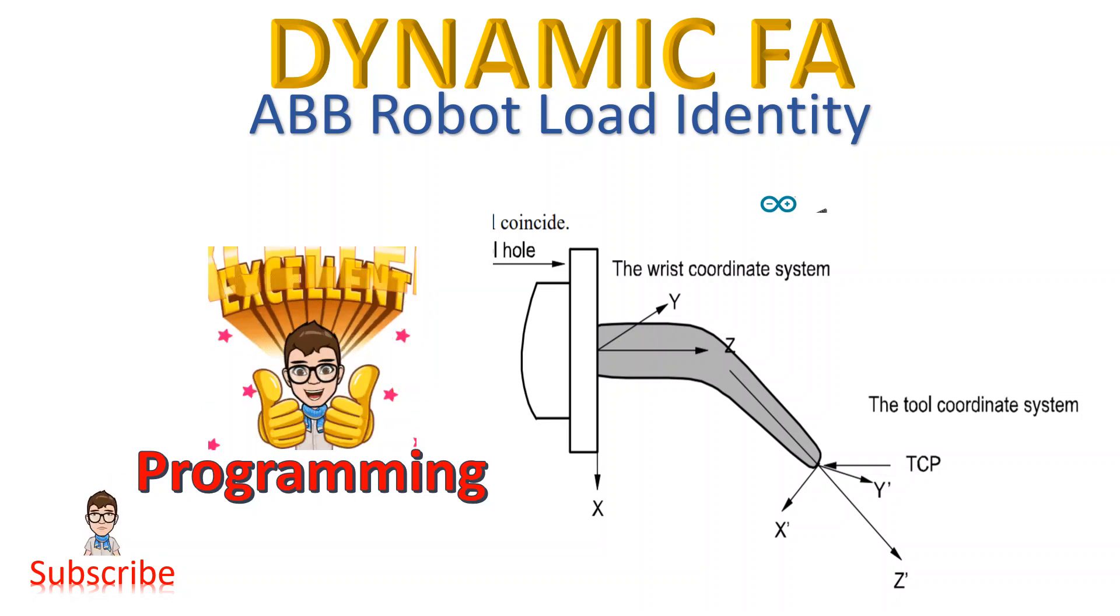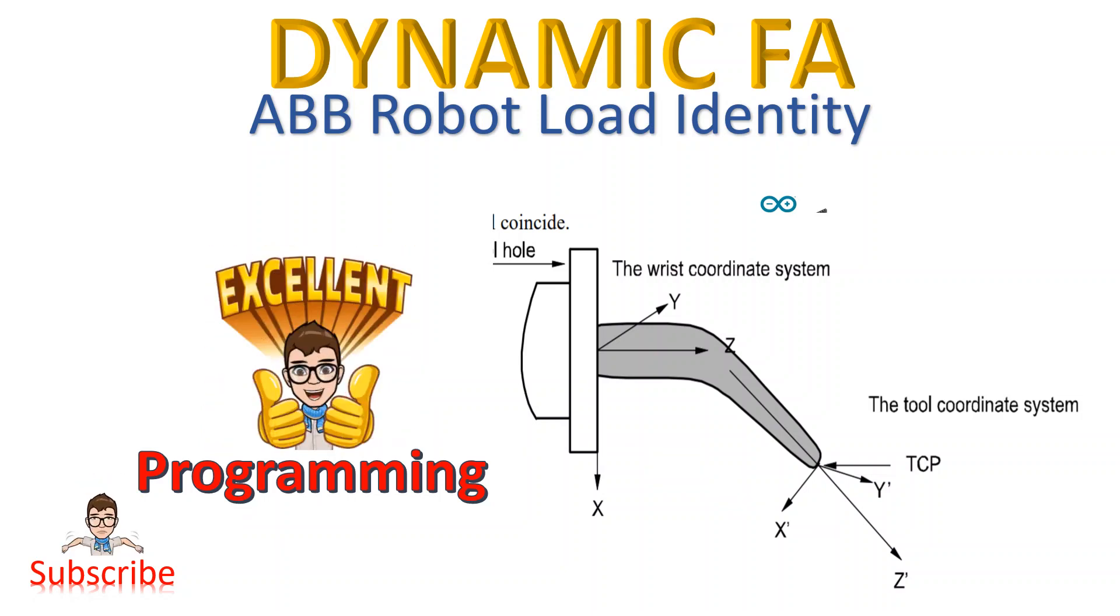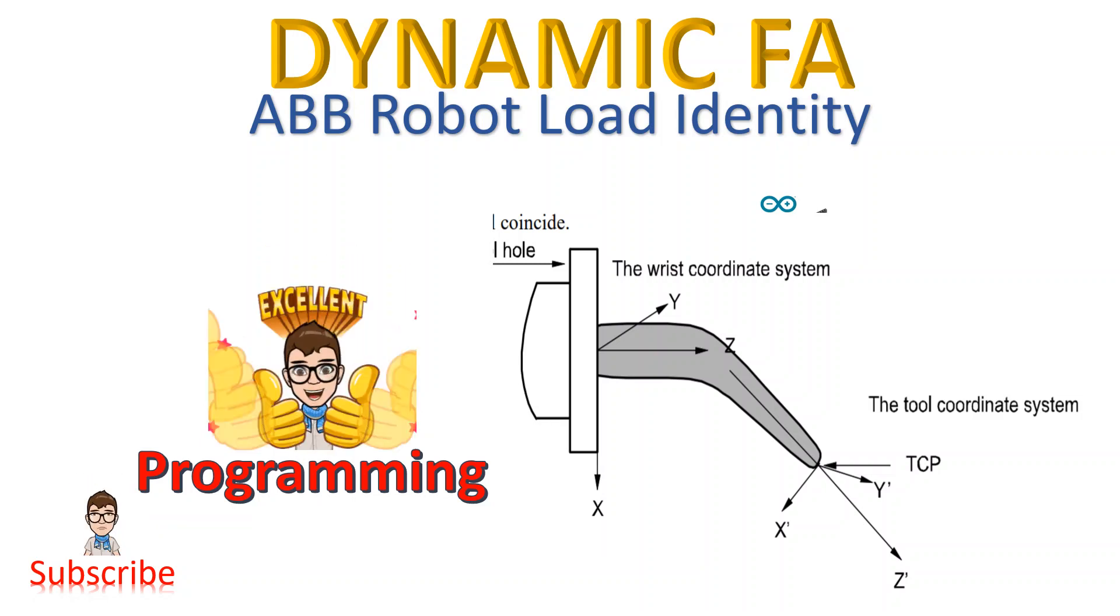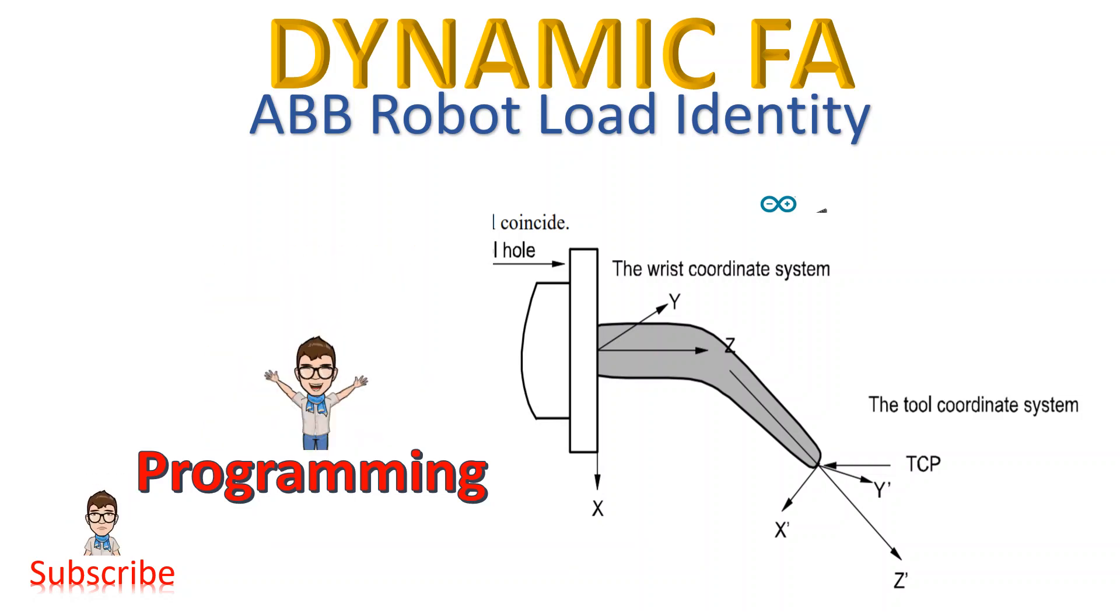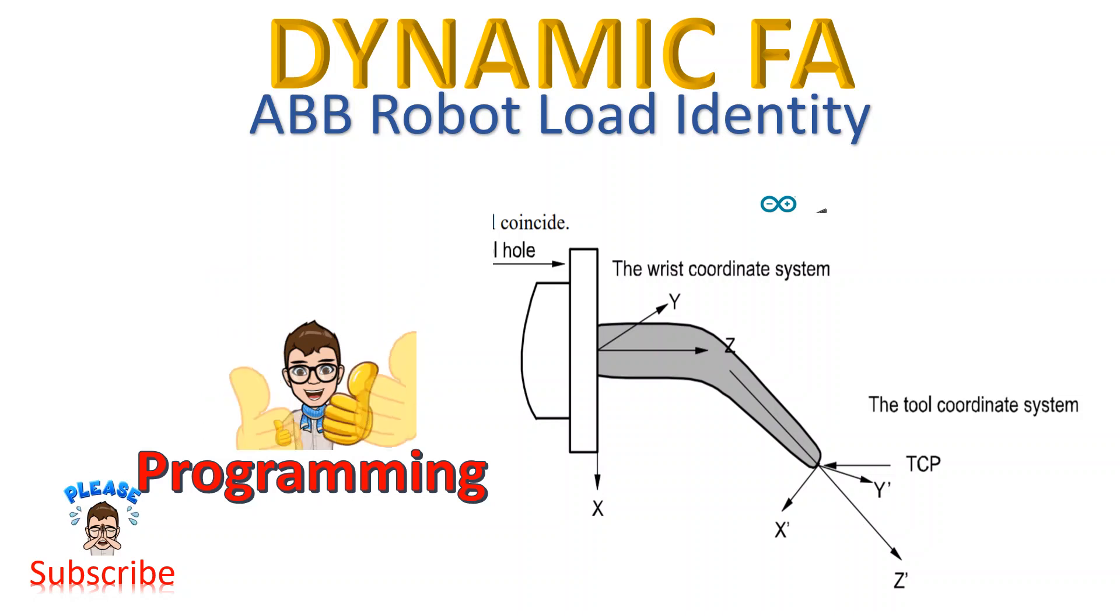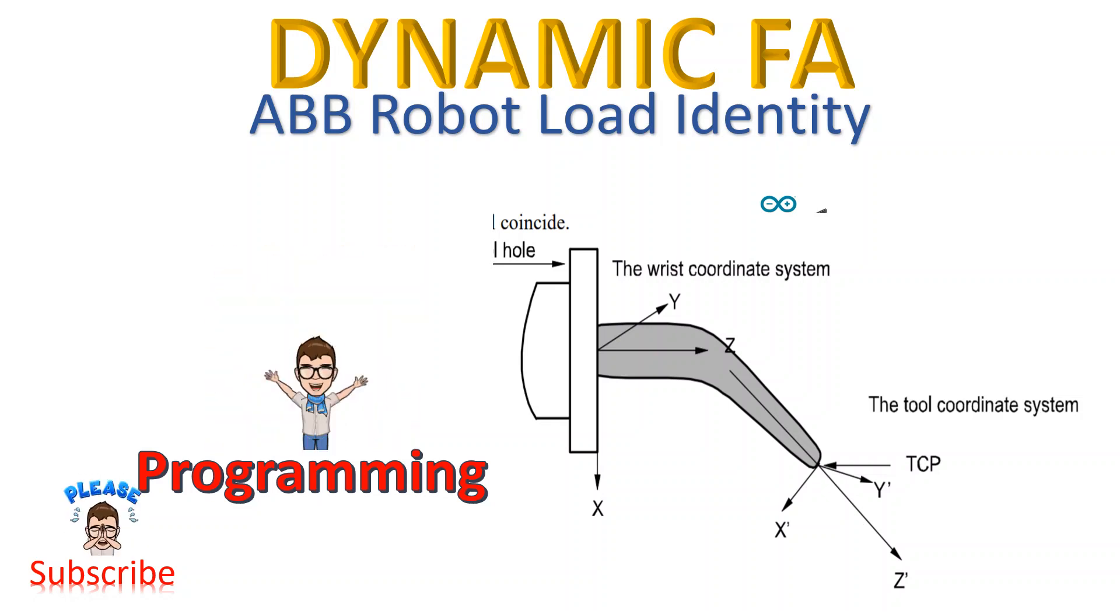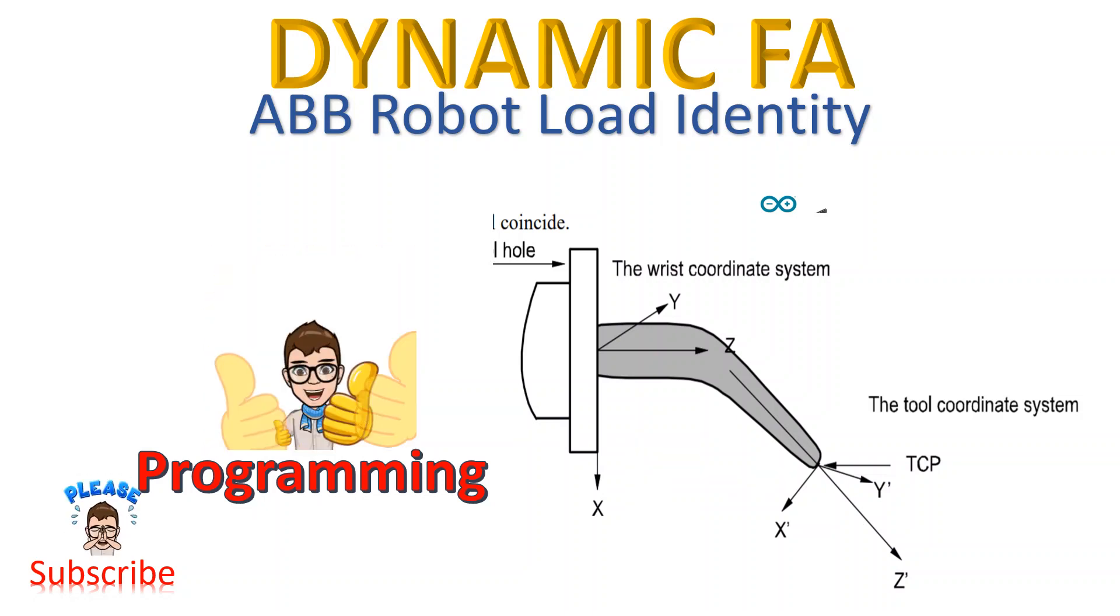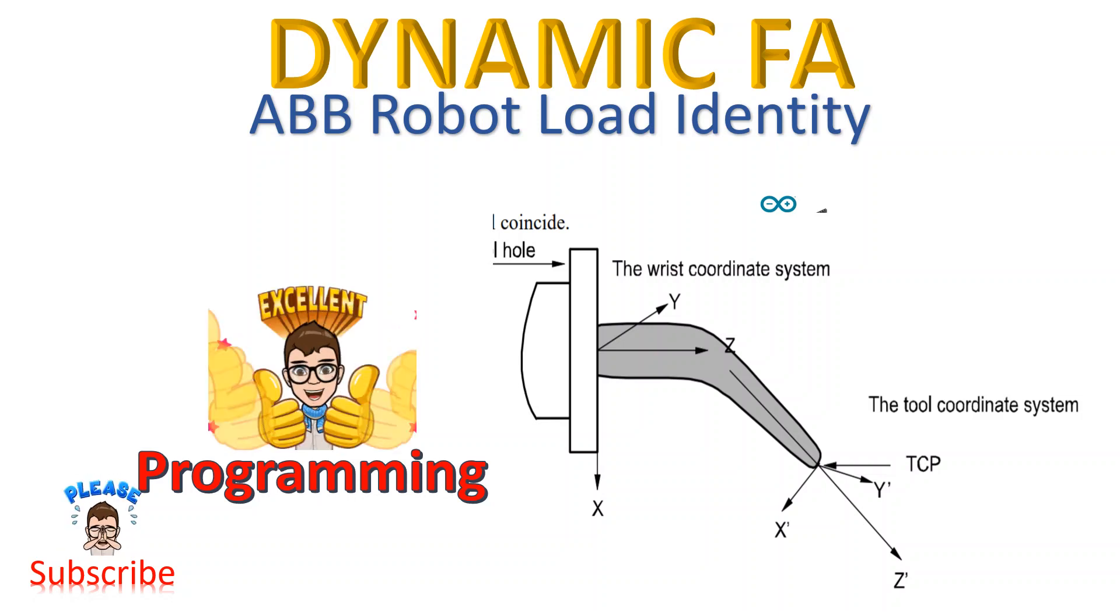Load identity is when you assign the tool and you have to enter the center of gravity, the weight of the tool, and also inertia. Because when you have a tool that's unbalanced, if you don't set it up properly, it'll make a serious problem for the robot mechanically and also it might lose the path and make a corner path failure error. So today I'm going to show you the service routine of ABB robot which can calculate the mass, center of gravity, and inertia. Let's look at the pendant.